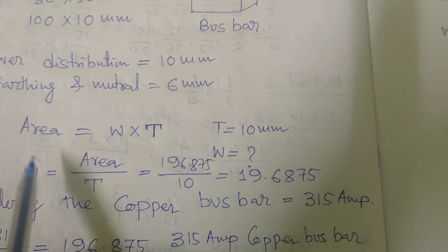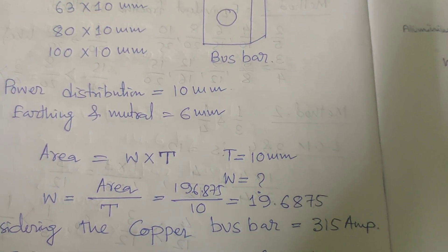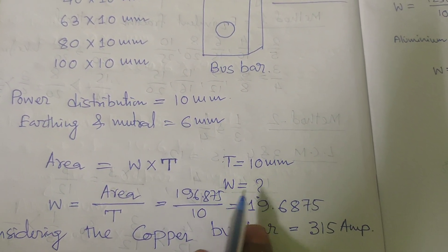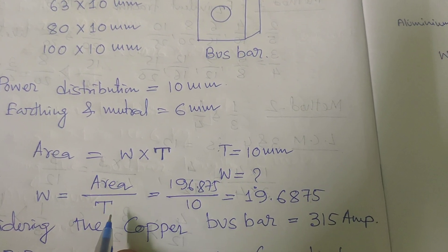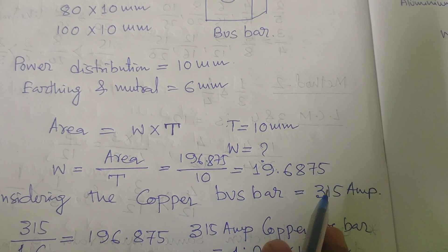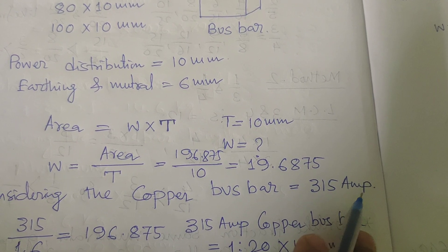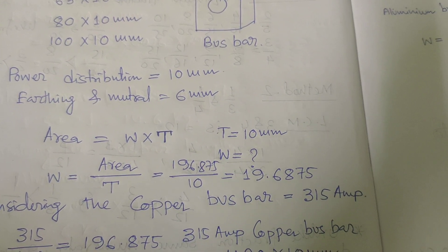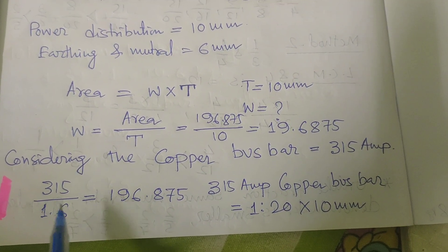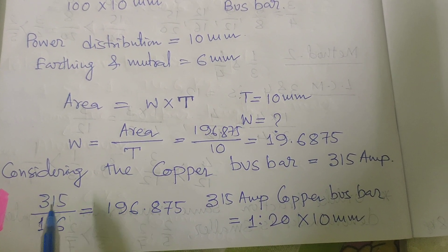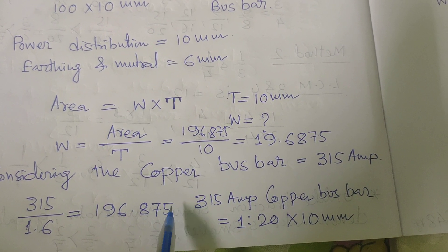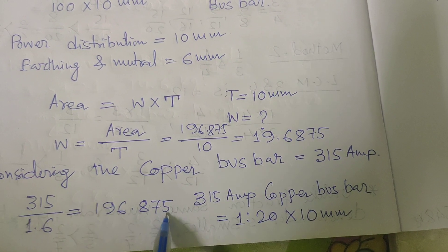Area equals width multiplied by thickness. So if the thickness is 10 mm, then width equals area divided by thickness. If we are considering a copper busbar of 315 ampere capacity: 315 divided by 1.6 (for copper) gives us 196.875 square mm.